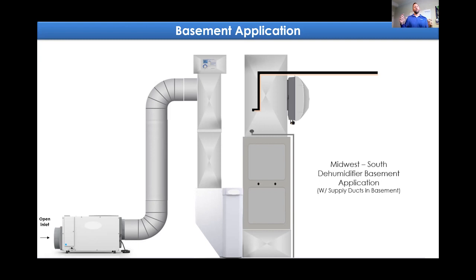But a lot of times there was a couple supply ducts that were dumped to just move the air into that basement. Now in the Southeast, that didn't happen. They actually have fully separate conditioning systems for the basements. But for Midwest, if you have this, a great way is just to have that dehumidification system inside that mechanical room or near that furnace area, drawing in the humidity at the lowest point in that basement where it's the highest, distribute it back into the return.